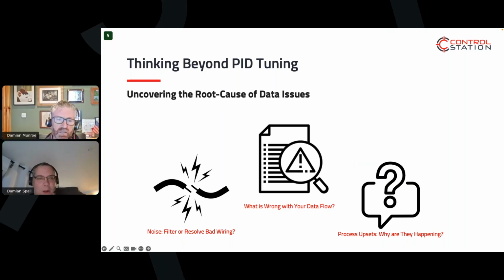Thinking beyond PID tuning, what could be causing the root cause of some of the data issues we experience? Noise, absolutely - it came through clearly in one of the surveys we did. We can do some filtering, but is there an opportunity to resolve bad wiring that could be causing it? Understanding what's wrong with the data flow matters. As engineers, we spend lots of time troubleshooting and problem solving, and getting to the root cause is very important - making sure we understand the data and the flows. And then, what's upsetting the process? Why is it happening, and why does it keep happening? What can we learn from deeper problem solving and understanding these root causes? Very important to consider.